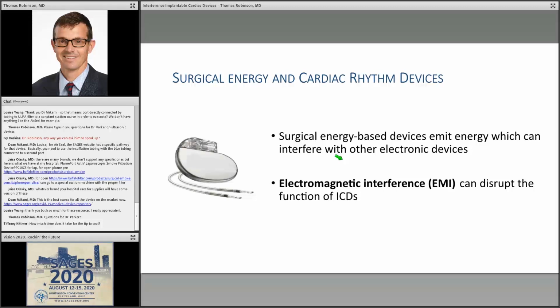And so when you hit the activation of the button with the bovie, your monopolar device, it causes electromagnetic interference. And you can see that on your video monitor. I don't know if anybody has seen it. Every once in a while when you activate the monopolar instrument, your video screen will become hazy, and that's electromagnetic interference. Because it has such high voltage, as explained to us earlier, it creates a lot of electromagnetic interference, and it disrupts the other electronic devices that are around it. If your screen gets a little hazy, that's okay, but if all of a sudden you don't trigger your pacemaker, that's a huge deal.